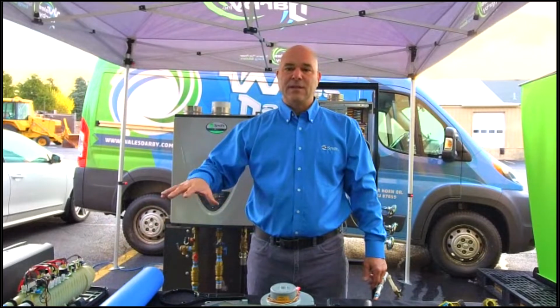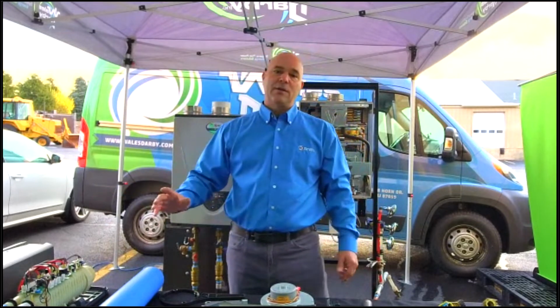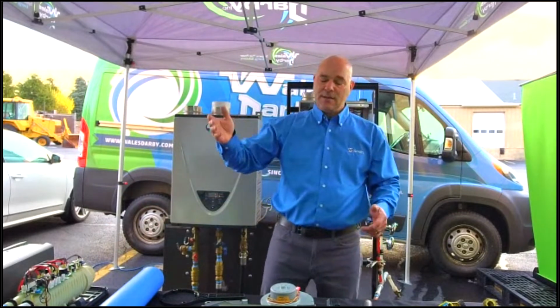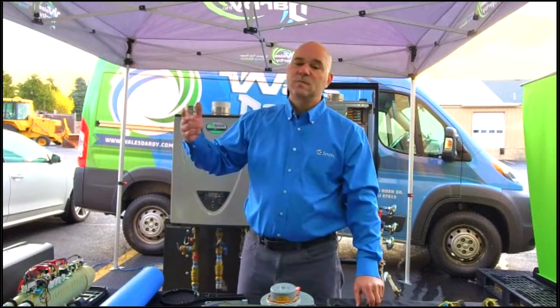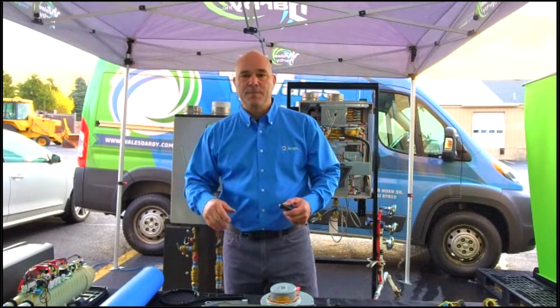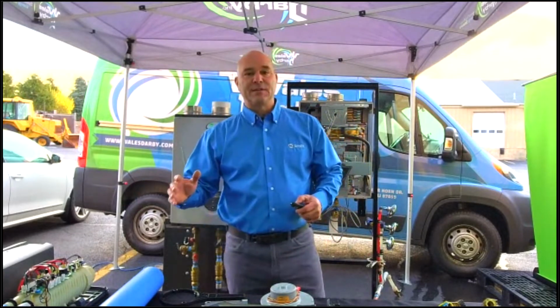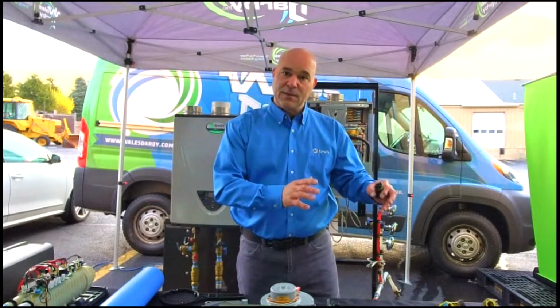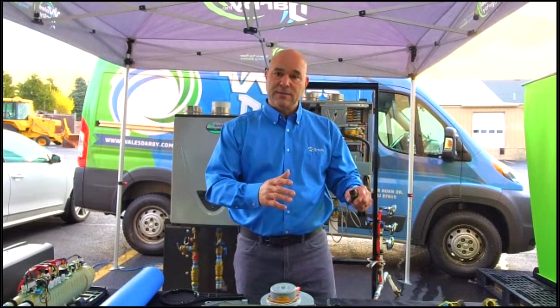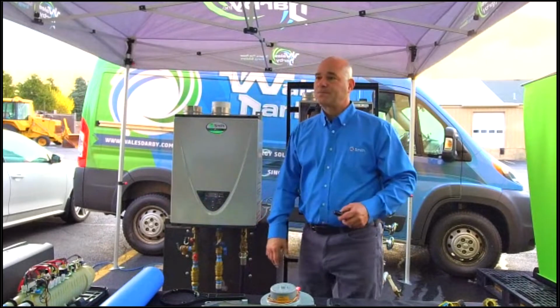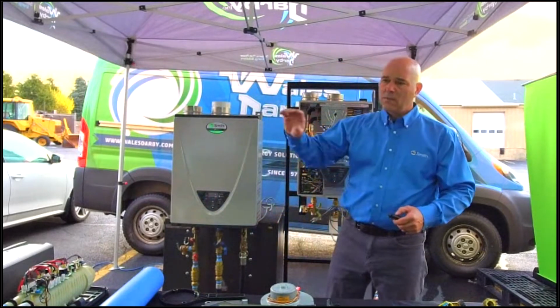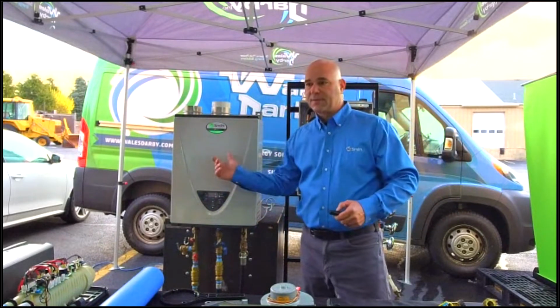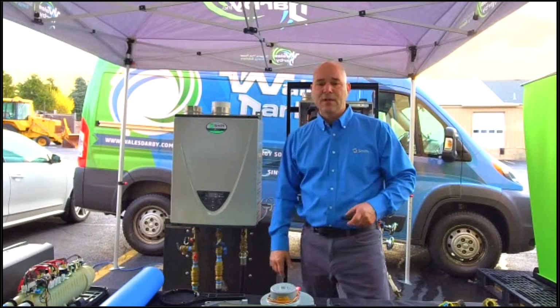And then usually in the tankless world, we look at a 70-degree temperature rise. And that's usually where we get our flow rates from in the tankless world, the 70-degree rise. On the tank style, we normally look at a 100-degree rise. Okay, so we'll keep rolling forward. We're going to transition from the electric to the gas, and we're going to dive in here.